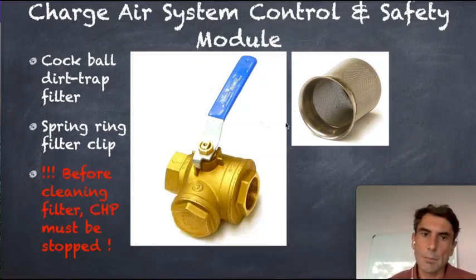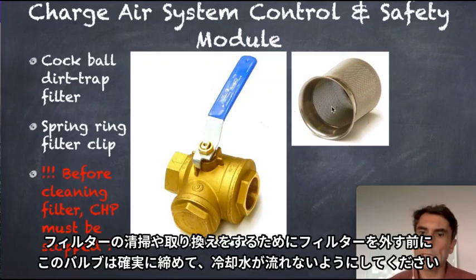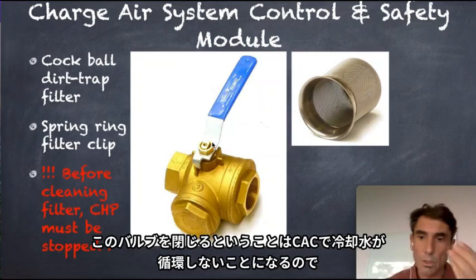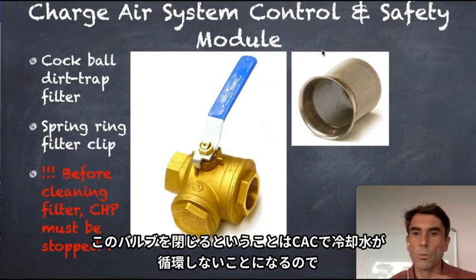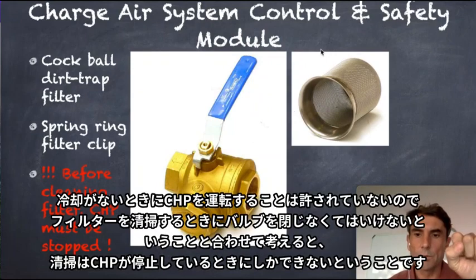So the filter itself is tied with a spring ring. It's around here. Important, if you would like to clean that filter, you have to close the ball valve. And that means, on the opposite side, if you close the ball valve, you will close the circulation of the charge air cooler water system. So if you close the valve to clean the filter, you have to make sure that you only do it if the CHP is stopped and not operating.